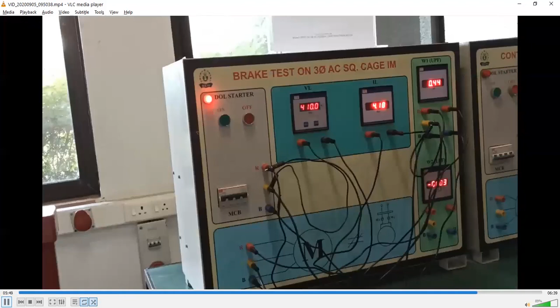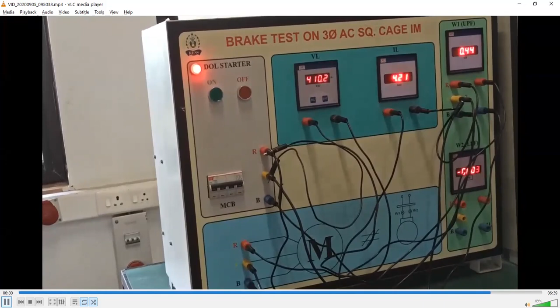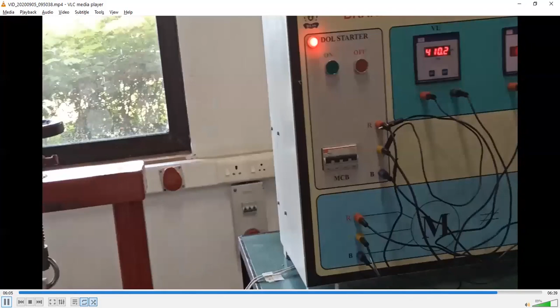Let me just show you those readings. Now please note down, this is a no load condition. So your no load voltage you should note down, 410. Your no load current is around 4.1 ampere and power is around 0.43 kilowatt. Second, you should note down we have not applied any load to the motor, and you should observe that zero load is applied to the motor.